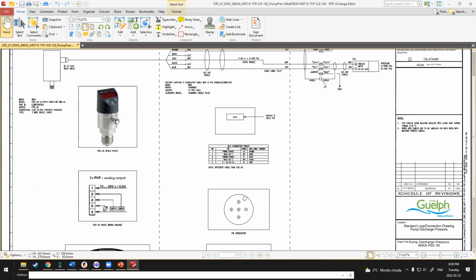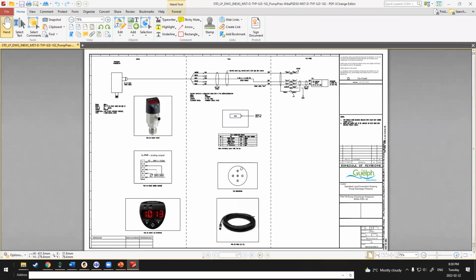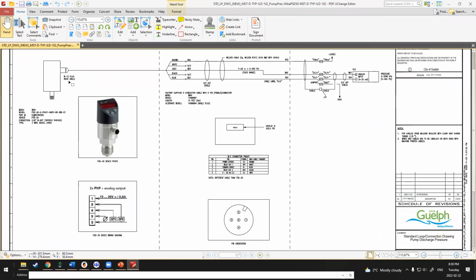Here's one of our pressure transmitters that gets installed. It even talks about ordering the one with the M12 plug at right angles, so it fits on our facility. It fits in all the tapped holes that are already in all the pipes. If we hand something to the millwright to put in and it's got the wrong thread, they'll throw it out. We'll have to order new ones. So sometimes it really behooves you to pay attention to what it is you have. If you're taking one instrument out and putting something else in the new hole, make sure whatever you're putting in that hole is going to fit. Make sure it's the right thread. That's not necessarily programming, that's just in general.